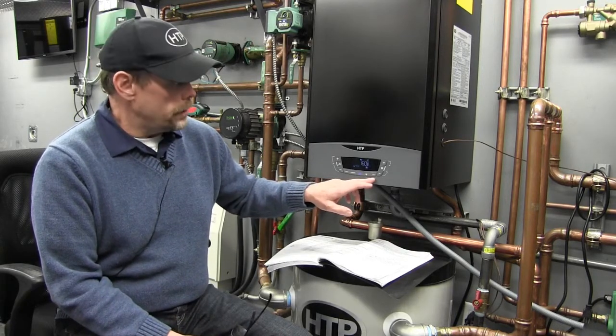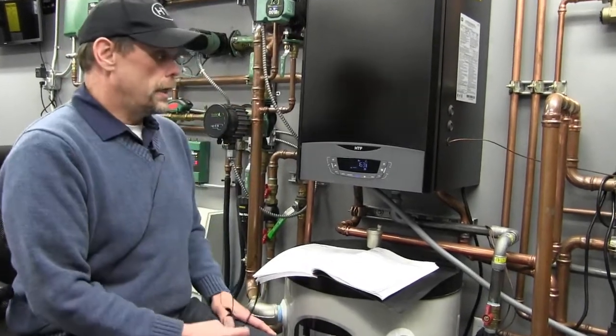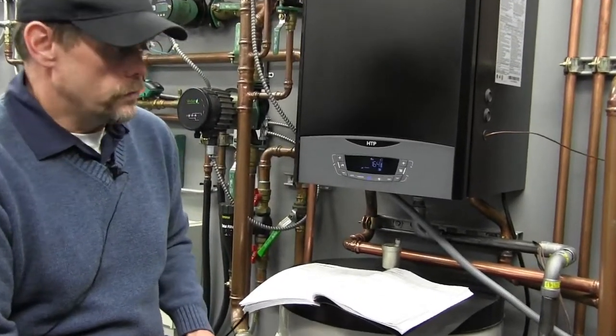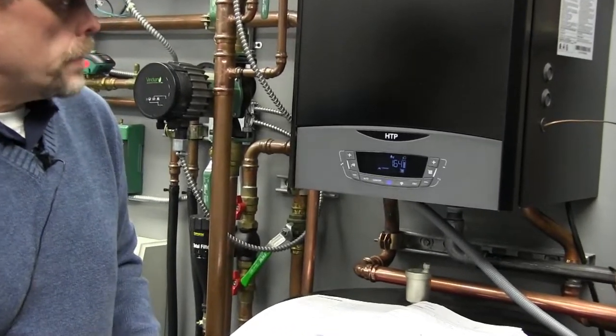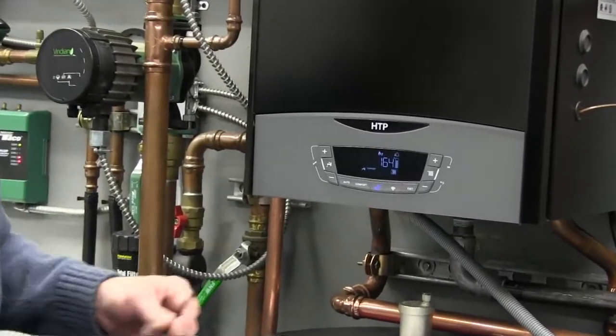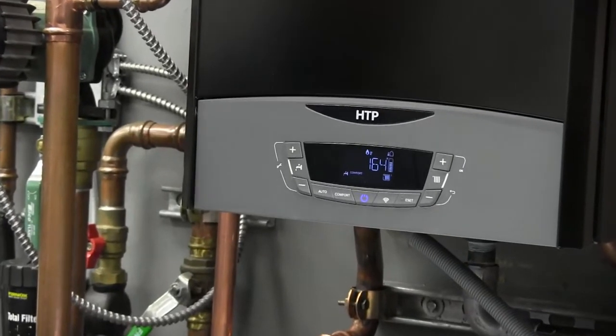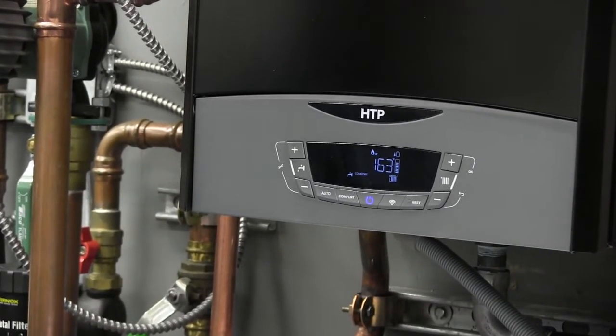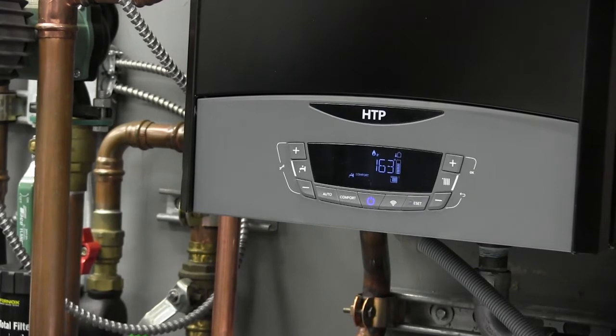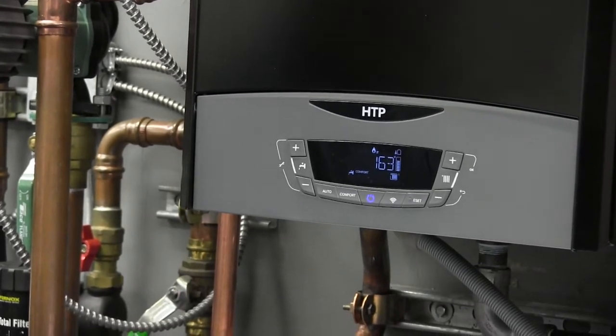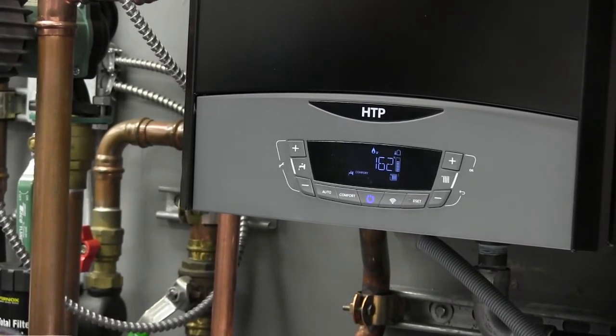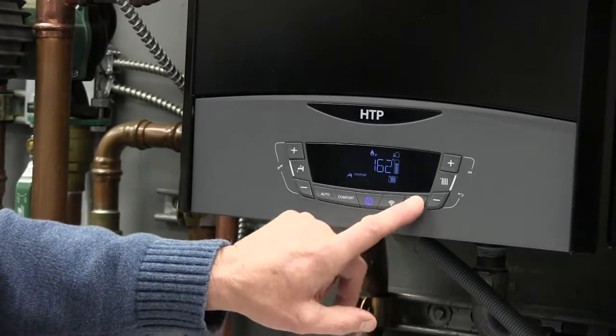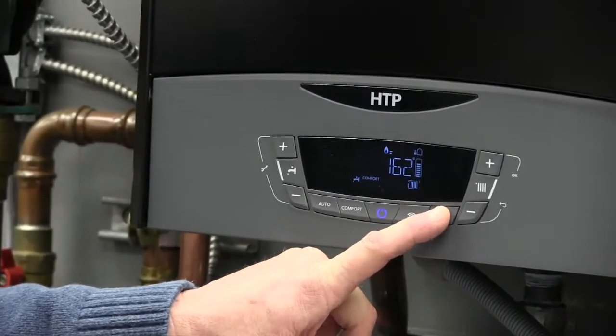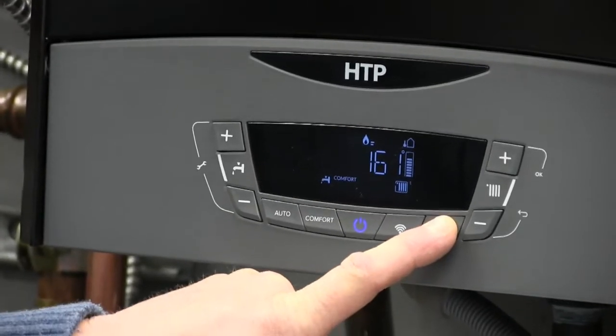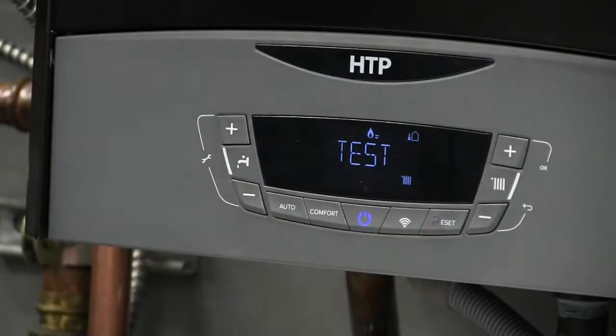The letter R in reset will actually backlight red and indicate that service or maintenance is required. The reset button is multifaceted, however. It does a second function: it's a quick access to our test mode. Test mode is for doing our combustion analysis and/or gas valve adjustments. So if we depress the reset button for approximately 10 seconds, we will see the word test.